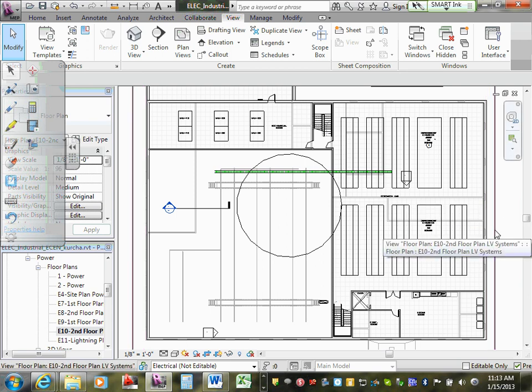We have a nurse call four-dome light that is in each bay on each side that they use for different colors. There's leak detection, gas detection, a manual emergency spill. The fire alarm system lights up a different color, and security or evacuation lights up another color. Because typically in there, they're not going to be able to hear, because they're in full gowns. So you have to use visual indication while you're in there.